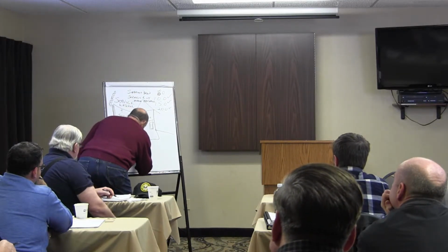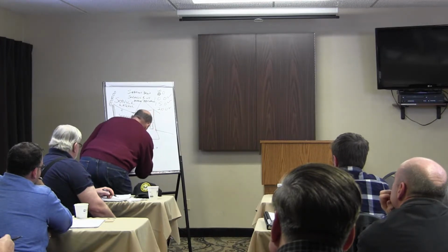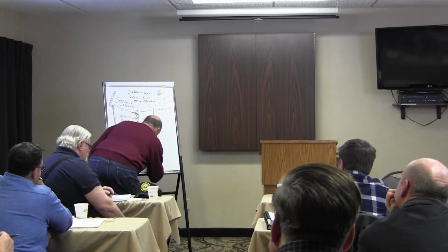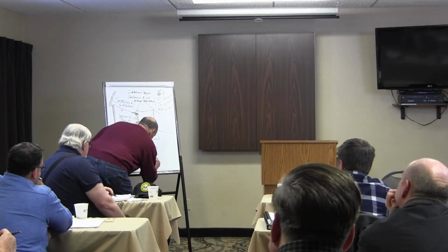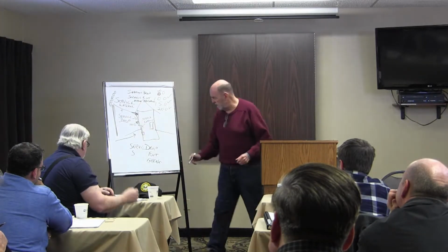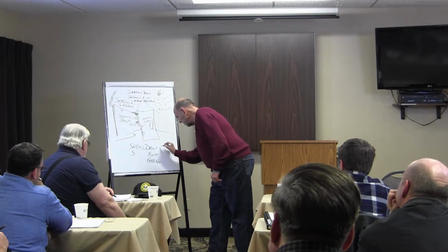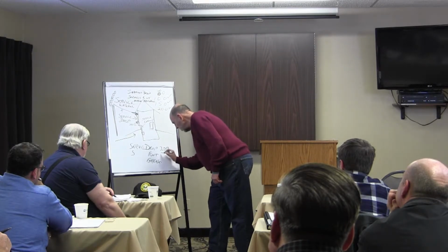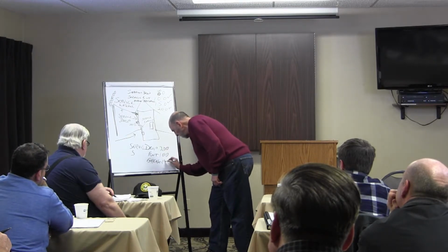So if I have a service drop, entrance, and breaker that is 200, 100, and a 150 breaker, what's the service size? 100. 100 amp. What defined it? Smallest wire. Smallest wires.